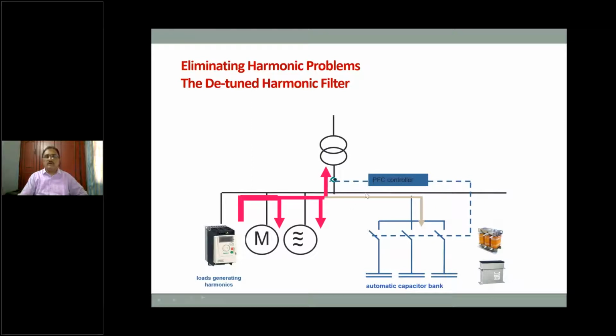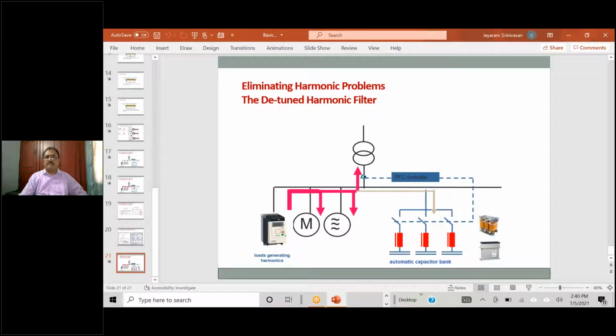So what do we do? A solution for this will be to provide a reactor upstream of the capacitor. So the supply will go via the reactor to the capacitor. When you do that, there is no harmonic amplification from the capacitor circuit, so that is avoided. Whatever was originally going will go to the network or grid towards the transformer and into the grid. So this has to be understood. That is the last slide I had. This is a simple understanding on harmonic.